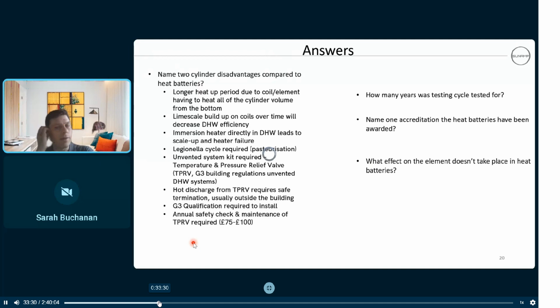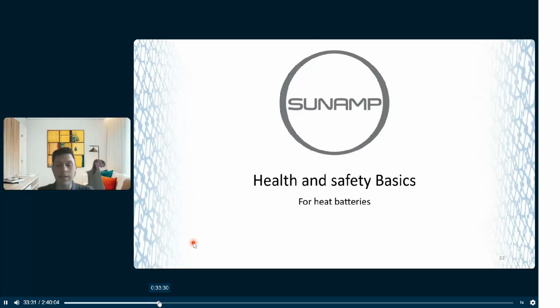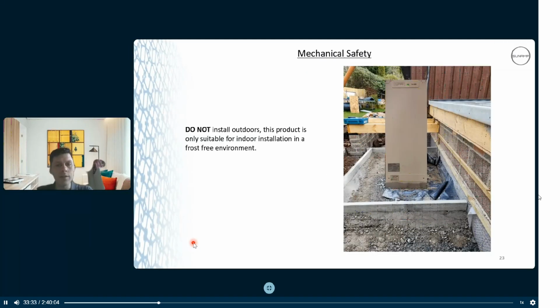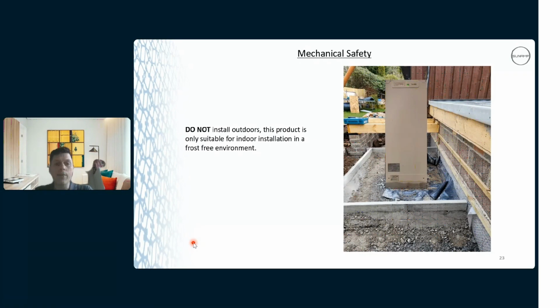But when it comes to heat batteries, somebody asked about fitting them in a cellar. We wouldn't recommend fitting them in an outdoor environment - it should be in a frost-free environment. We do suggest it's fitted in an indoor installation only. So obviously the thing to consider would be frost if it's fitted outdoors, and high heat losses as well.